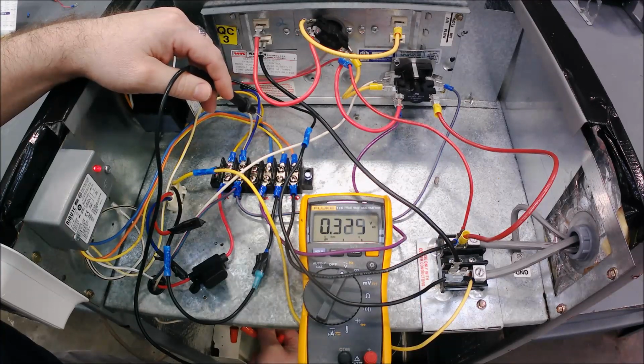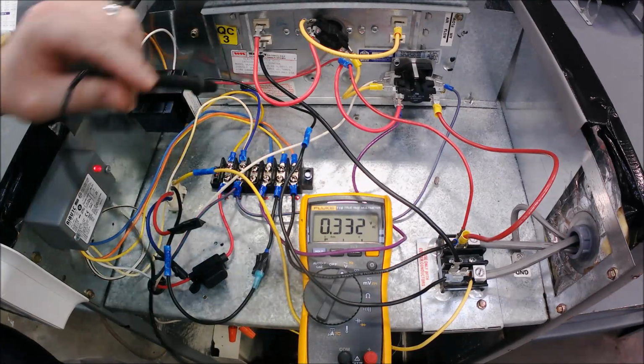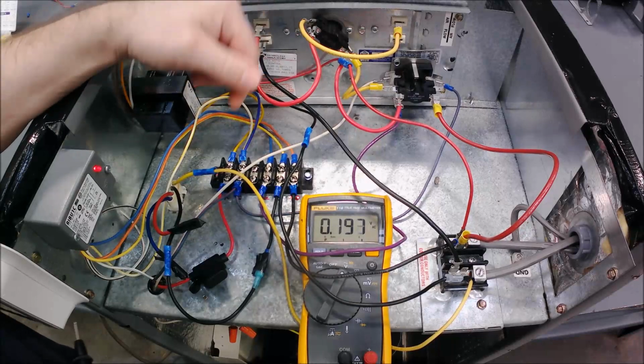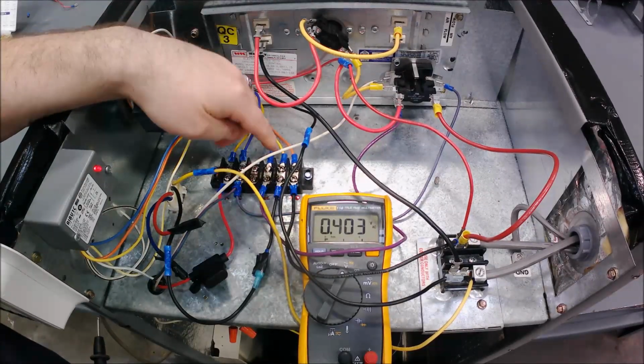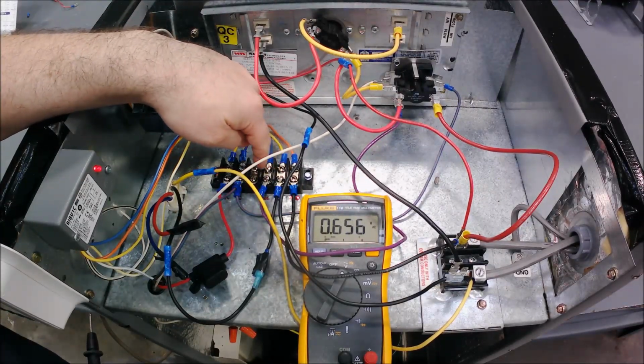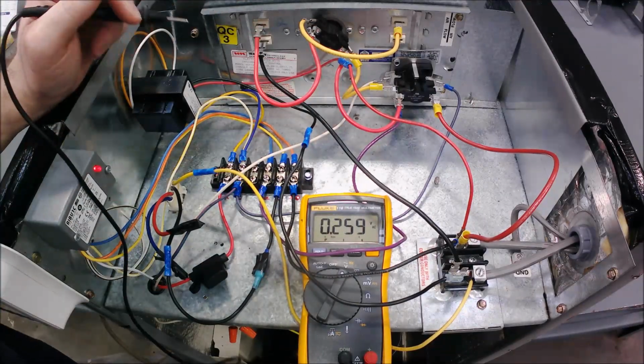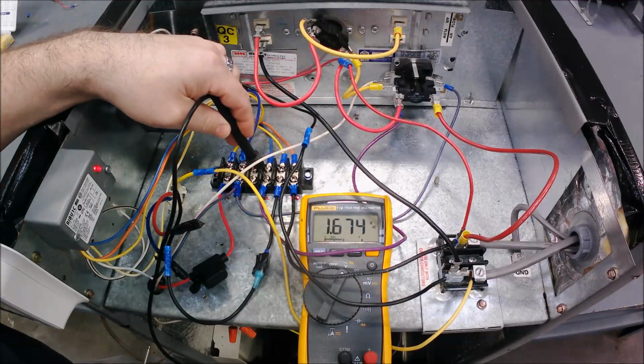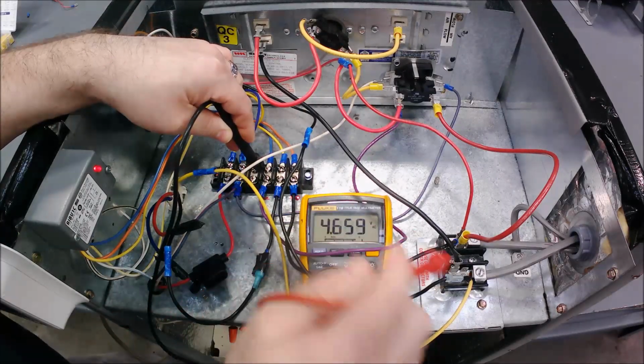So what if the fan wasn't working? Well, you have to remember that just like on the 9340 relay, all of these terminals for the switching side of that rib are just one side of power. So if I check here, if I check the L1, it's going to say 0.